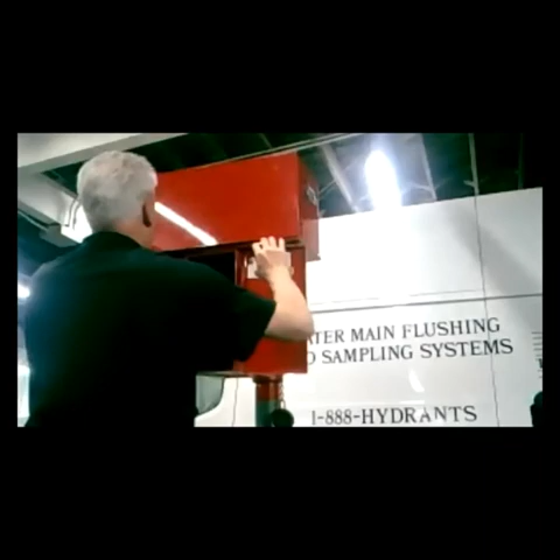Question is, do the intelligent monitoring and flushing devices work for utilities using chloramines as well as free chlorine? Good question. With chlorine, you have a choice of three different sensors: free chlorine, combined chlorine, or total. We do have some systems around the country and in Canada that do what we call a free burn, using combined or chloramines most of the year, then switching to free chlorine for a short period to burn out biofilm in the pipes. They actually swap sensors in and out depending on what they're doing at those times. Standard with the unit we offer free or combined chlorine, with a bit of an adder charge for total chlorine. So we can do any of those three.